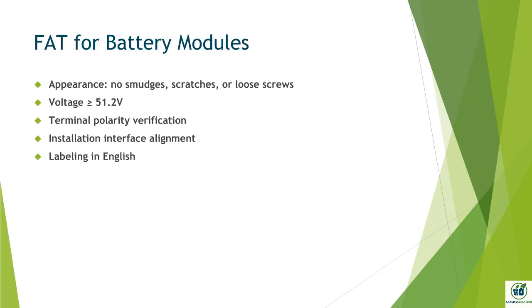Battery modules undergo a thorough inspection. We verify that the appearance is clean, labels are legible, and there's no physical damage. Voltage readings must meet or exceed 51.2 V. Terminal polarity is checked to prevent reverse connections. The installation interface is assessed for alignment and secure mounting. These checks ensure safe and efficient energy storage.